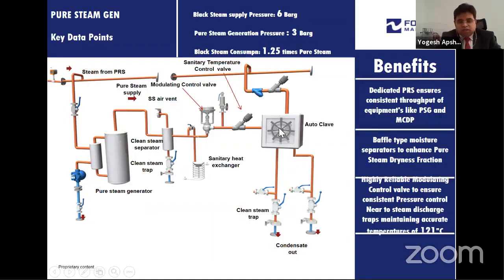In the autoclaves, in the chamber, we have to inject live steam, which has to maintain a temperature of 121 degrees Celsius for a period of 40 minutes or 35 minutes. While in the jacket, we provide black steam with a process trap, which will maintain the temperature in the jacket, and the pure steam will maintain the temperature inside the chamber. So this is the way we recommend the ideal hookup for the pure steam generators, pure steam distribution, pure steam utilization, and pure steam condensate.